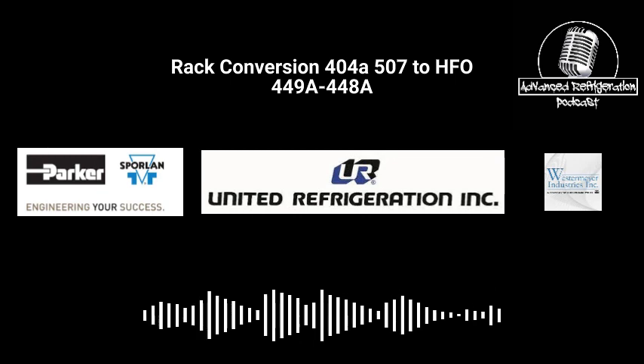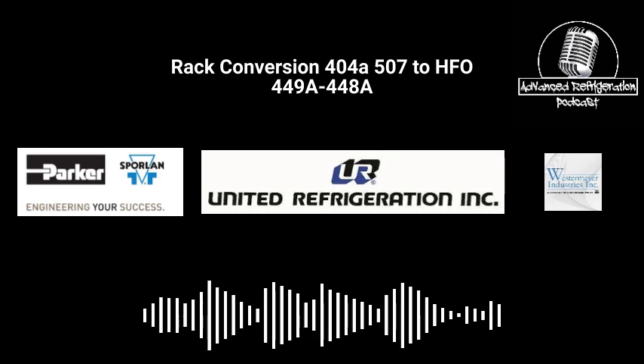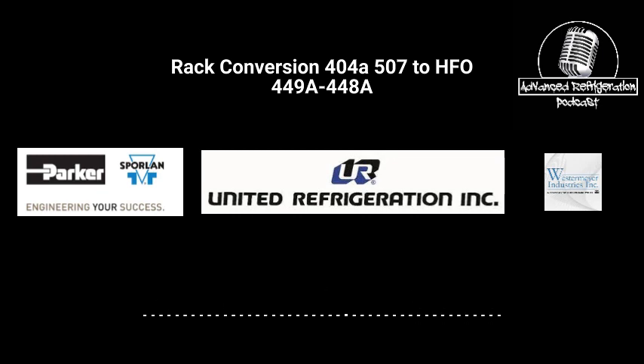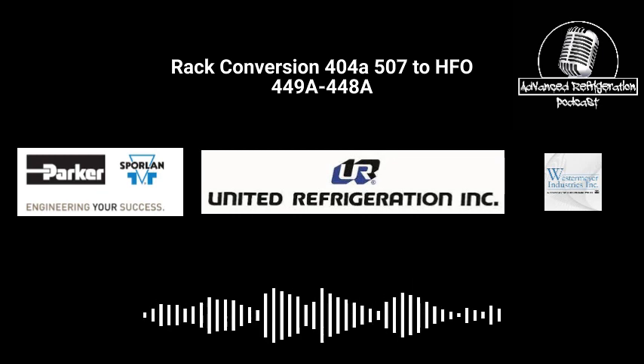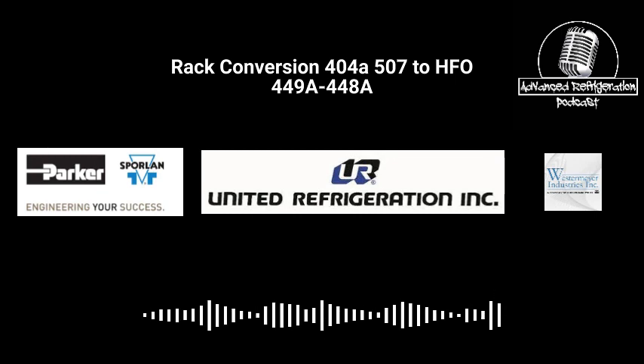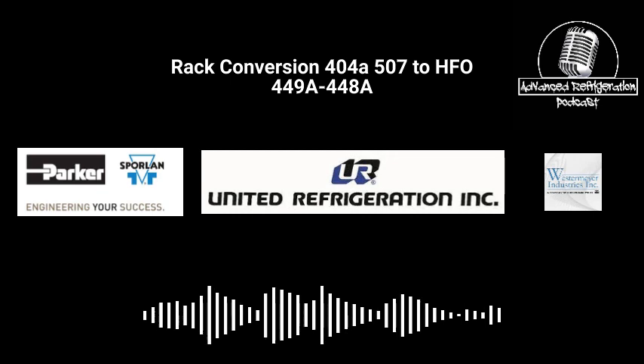There's also pressure transducers on there, and I forget what they're for. I think it's for the digital unloading, so it can modulate based off suction pressure. So you could have it on a single system and digitally control that compressor. I don't know if it can do that. I'm sure it could. No, it can, because I remembered at the thing in Cali, I went to one of the Bitzer classes because I wanted to know more, and the guy was saying you can put pressure transducers on there. I asked what for, and he said typically you're just sending a signal from the BMS system, but in this instance you can put a pressure transducer on the suction and discharge and basically cut it off if it's too high.